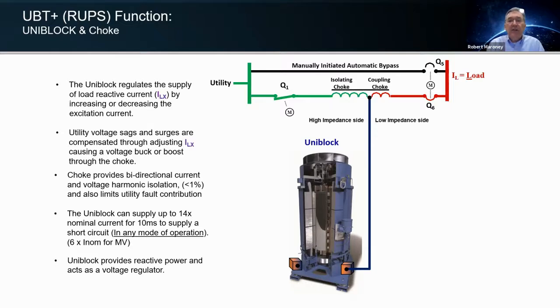If I'm going to deliver VARs to the load because voltage is starting to fall, for example, and I want to buck it back to 480 nominal, plus or minus 1% per specification requirements, that flow of reactive current is going to flow to your load through the coupling choke, because it's a lower impedance, right? If we have voltage sags, the uniblock monitors those voltage sags.